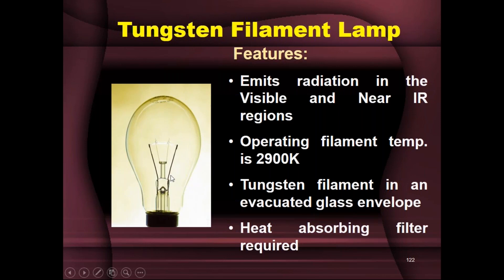Since the bulb is made of glass, you can get only visible radiation. Any UV radiation emitted with wavelength shorter than 320 nanometers will be absorbed by the glass. So this tungsten filament lamp emits radiation in the visible and near-IR regions. The energy distribution of this lamp is temperature dependent, and in most cases the operating filament temperature is 2,900 Kelvin, at which the lamp emits in the visible and near-IR regions.